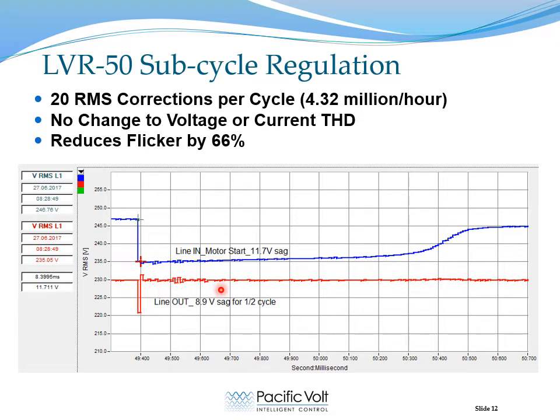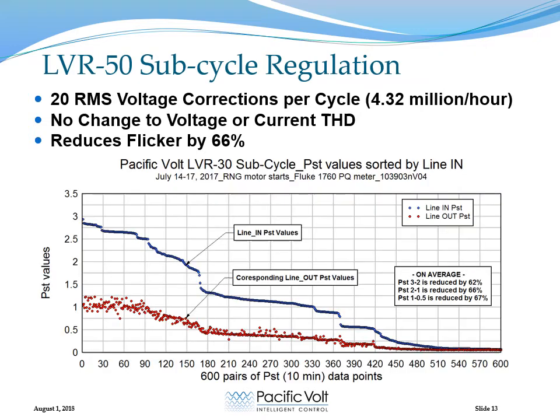1/2 of 1 cycle. To put the flicker reduction in more quantifiable terms, the chart below plots 600 PST values. The PST on the input to the regulator is in blue, and the PST on the output of the regulator is red, and each pair, input and output pairs, are plotted in descending order in this chart. We used to share a distribution transformer with a cabinet maker, and they thoughtfully provided us with many motor starts every day, and that's how we collected this data.